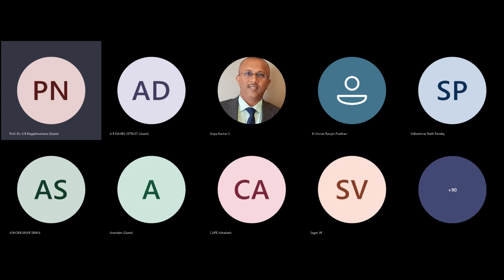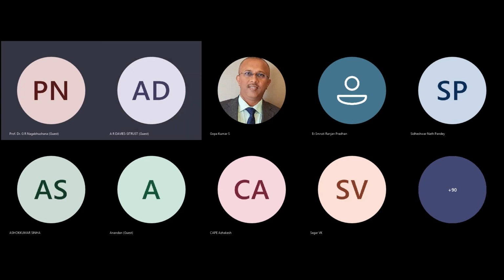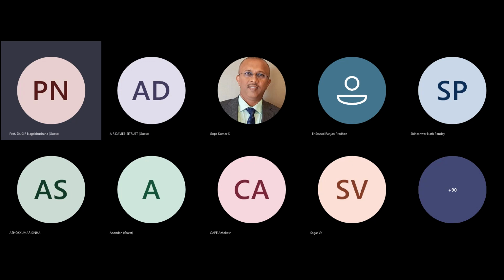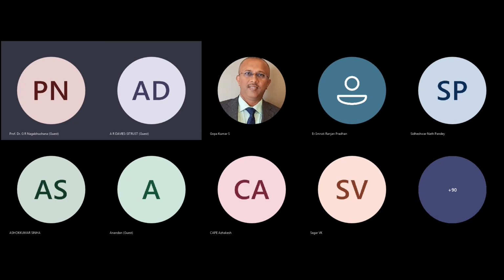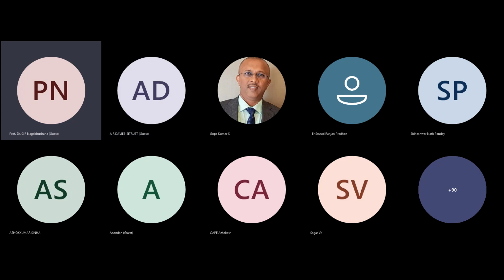Now, supposing there are about 4 insulator strings between the point struck by lightning and the station. If the first insulator string does not flash over, because it's only 50% probability, the second one may. If the second also does not flash over, the third may. So the probability of flashover increases very much, and finally what is left is only the 50% flashover voltage. If there are at least 4 strings from the point struck to the transformer station, then we can say with almost certainty that the voltage coming to the transformer terminal will be approximately equal to the 50% flashover level, the critical flashover voltage, of the insulator string. So the insulator string has to be designed very carefully, because the transformer and surge arrestor selection depend upon it.